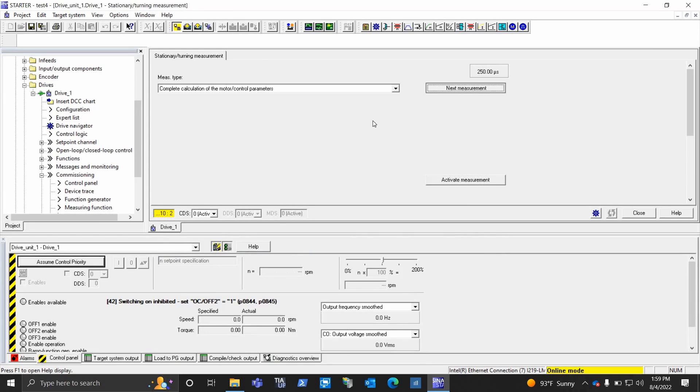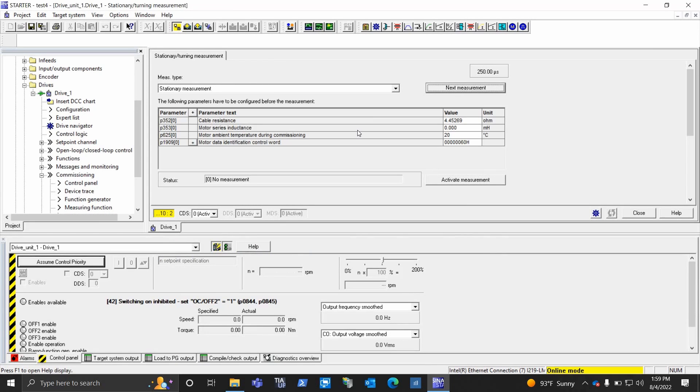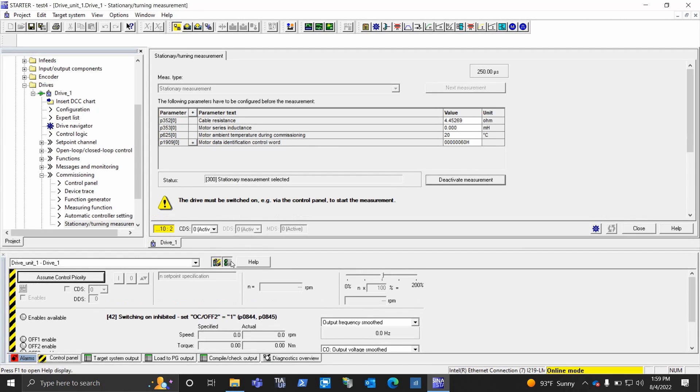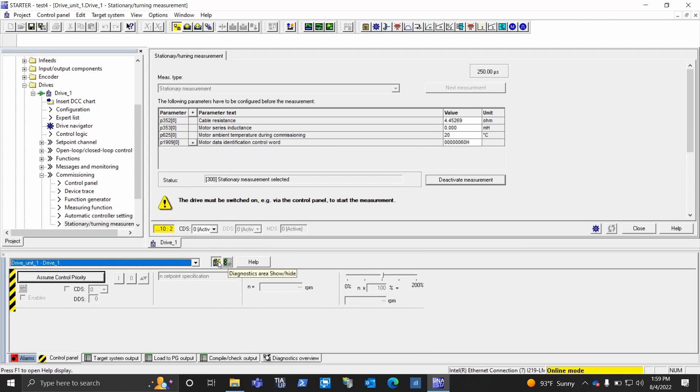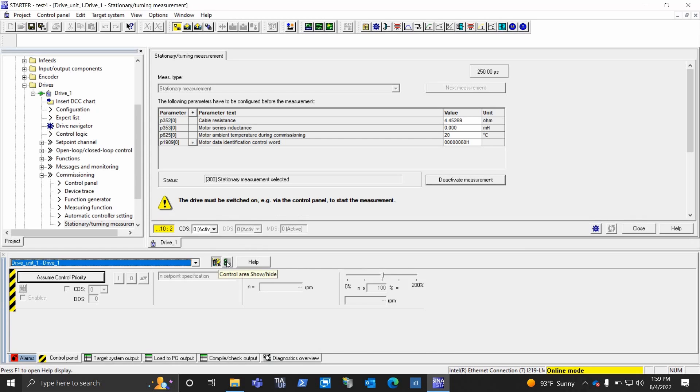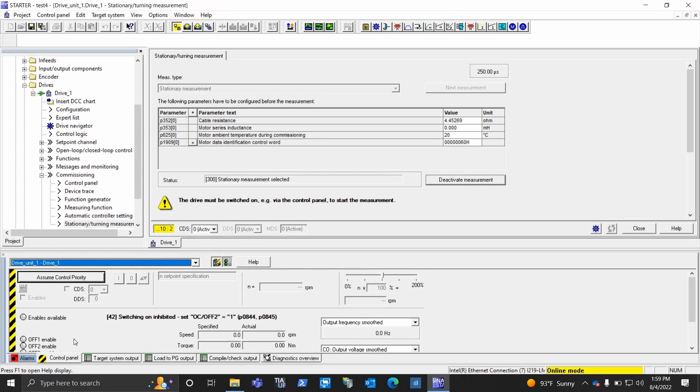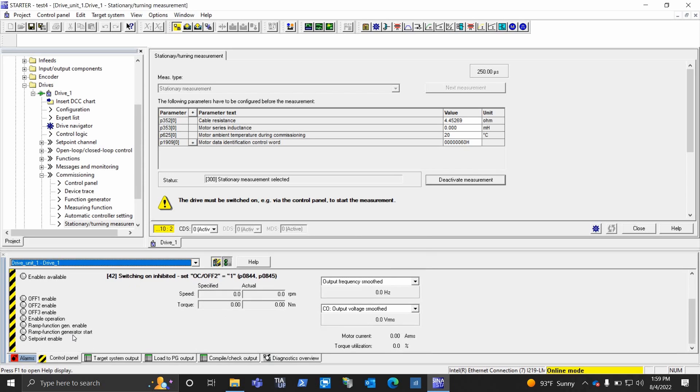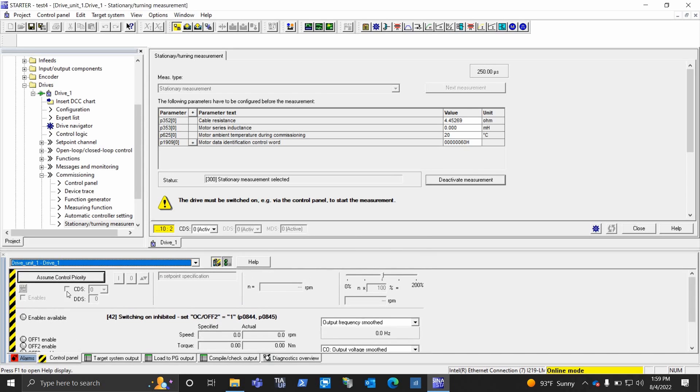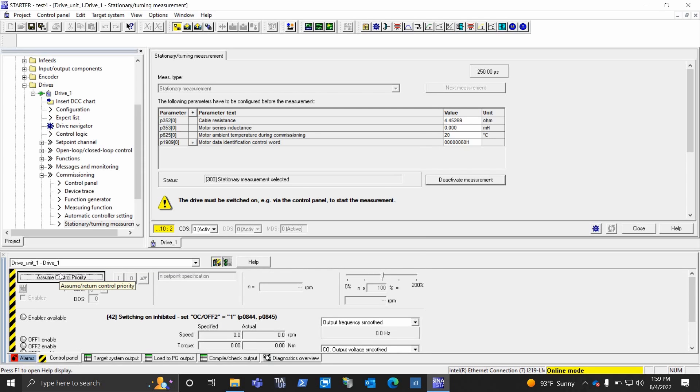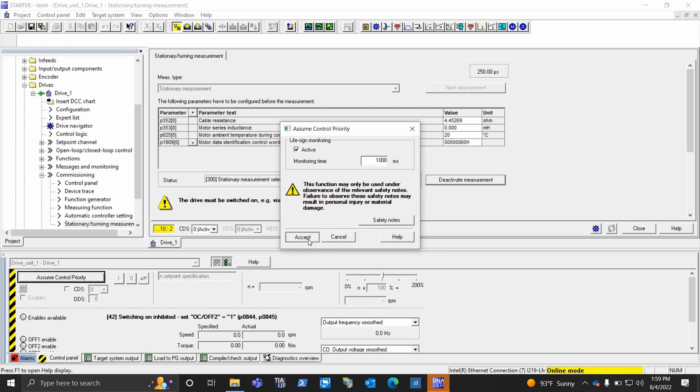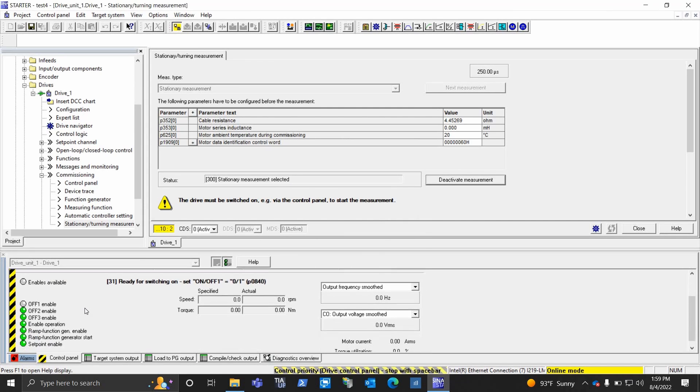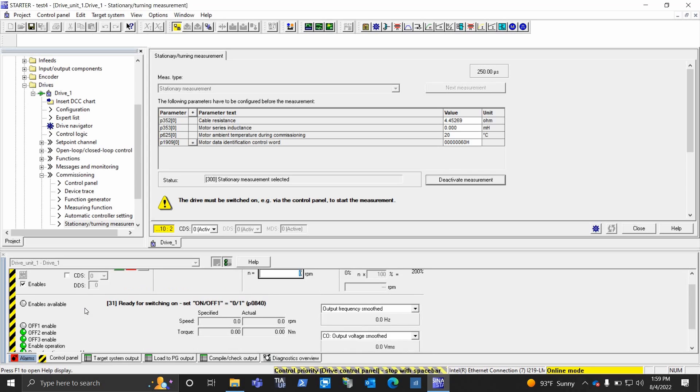And the next tune is I got to fire the drive up, so I hit next. It's going to be the stationary. Stationary, it's going to run some current through the motor. It may jiggle, but it won't actually spin. I'm going to activate that. Now I got to take control of the drive and make sure you click these two little buttons so you can see everything. I don't know why they're not on by default when you have a new installation. I'm going to assume control, so it's warning me that we're going to be spinning it, taking control of this thing. And now I'm going to enable all the enables, which you have to do when we're running it manually here.